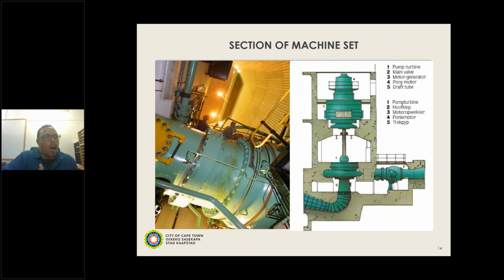We can operate without the pony motor in generate mode. It will simply take a lot longer. So instead of shutting the machine down in approximately 4 to 5 minutes, the machine will run down on its own weight, still on the bearings that are lubricated and under air pressure. And that takes anywhere from 15 to 20 minutes, depending on the different characteristics of the bearings in each individual machine. So that's the one purpose that the pony motor serves. So we can generate without the pony motor.